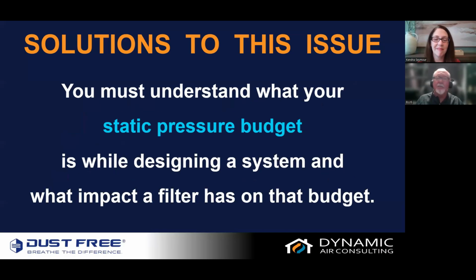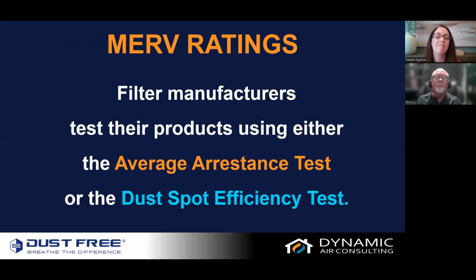So that's a basic explanation of a static pressure budget. And then what effect does the filter have on that budget? So let's talk about MERV ratings, because we hear the term thrown around a lot. And it's interesting, 3M, I think they're actually giving MERV ratings now. They didn't used to. They used to give their filters a star rating. And certain, oh, this is a 5-star, or this was a 3-star. And then they very quietly, because they were trying to buck the system, started adding MERV ratings, because that's the standard which we all have to follow. So they got on board.